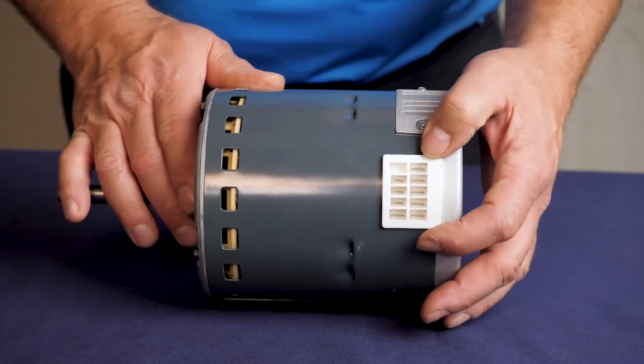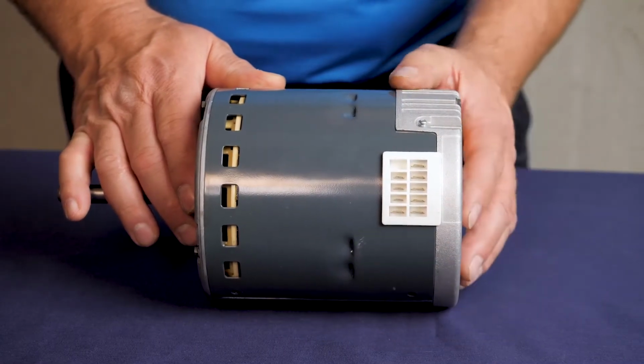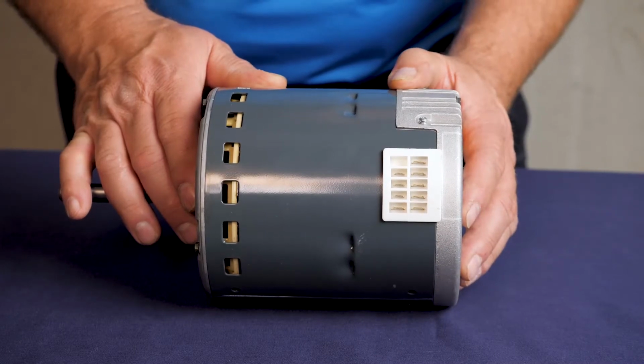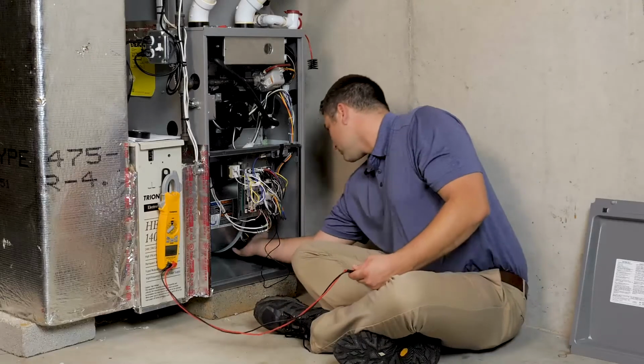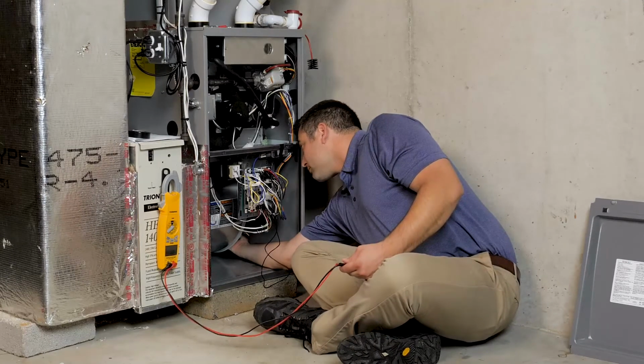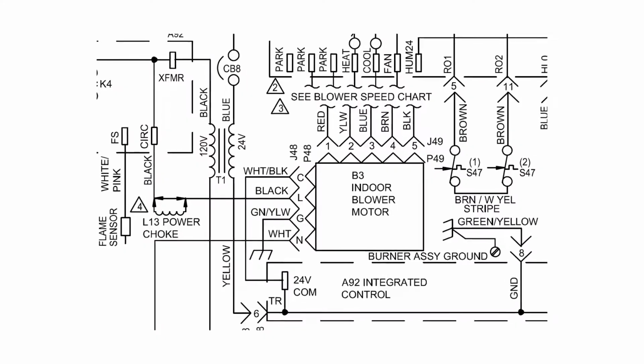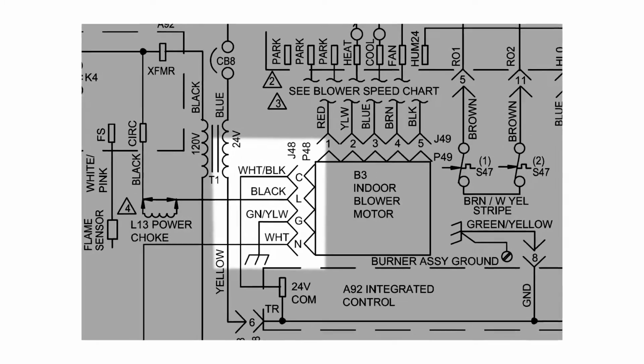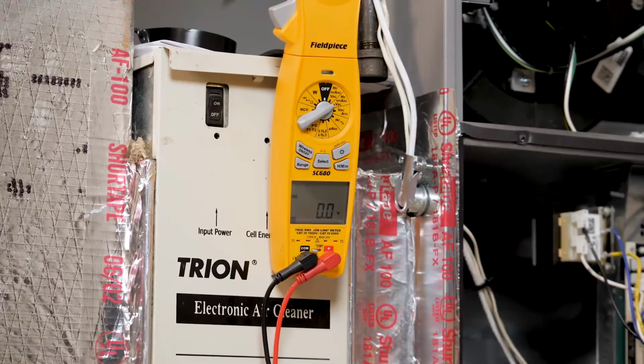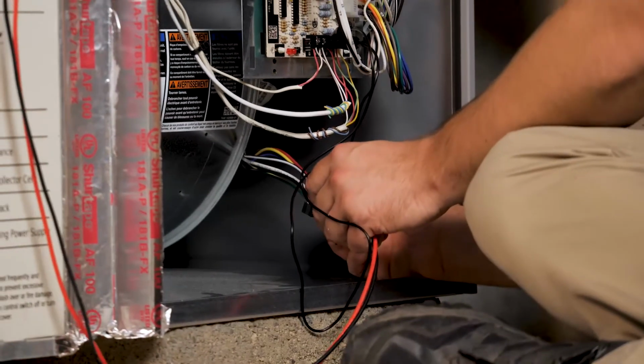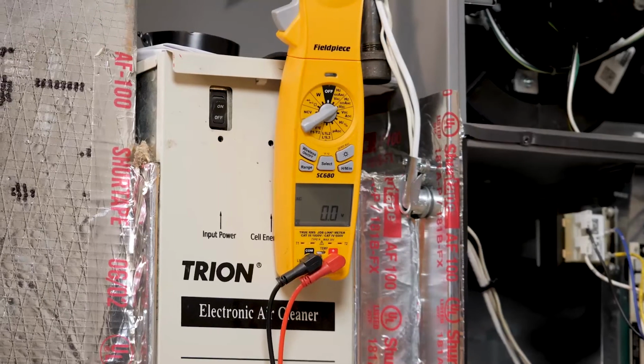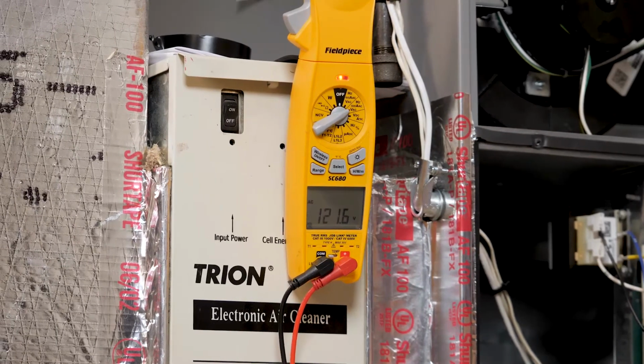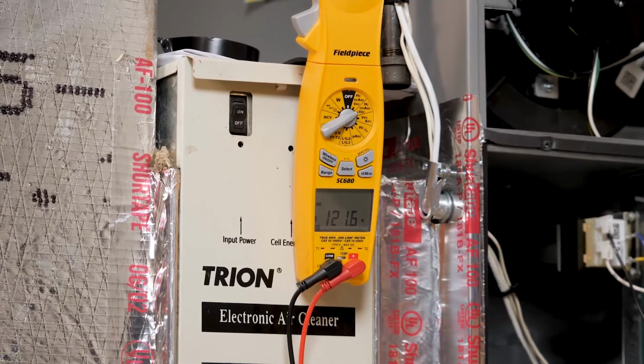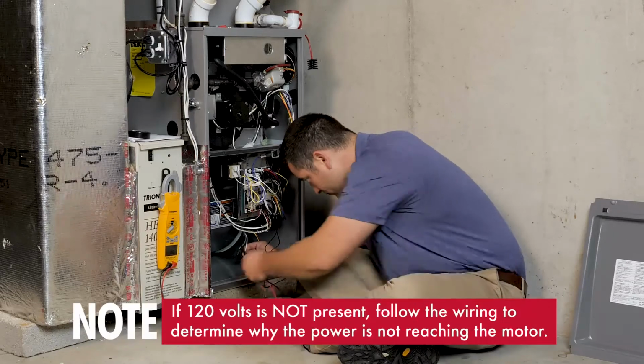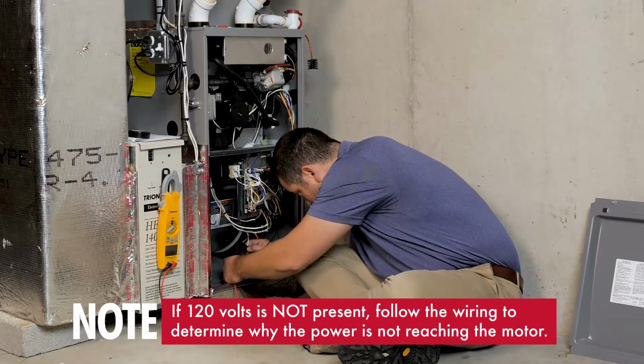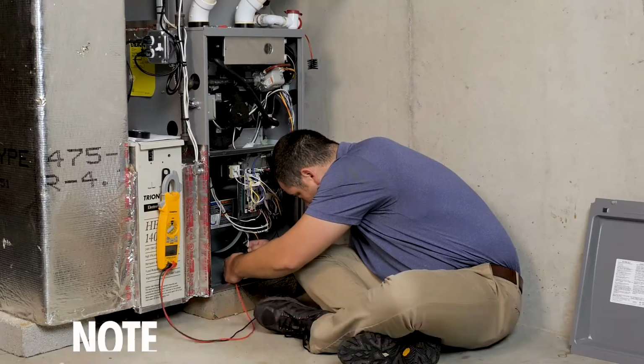We will start with the X13 constant torque motor. The constant torque motor is very easy to troubleshoot. First, you will have to confirm that the high voltage 120 volts is being supplied to the motor. You'll have to follow the wiring diagram to locate the high voltage to the motor. Then, using your multimeter set to AC volts, test between L and N to see if 120 volts is present. If there is 120 volts present, you can continue to troubleshoot the motor. If 120 volts is not present, follow the wiring to determine why the power is not reaching the motor.